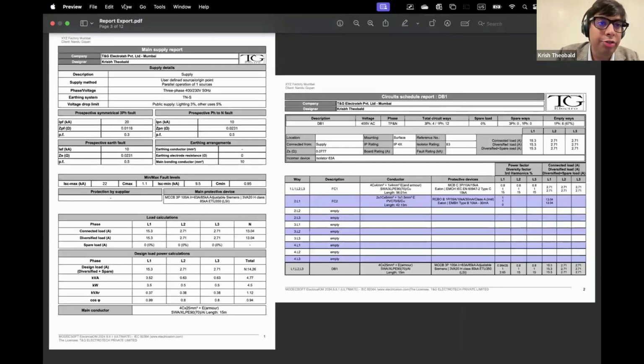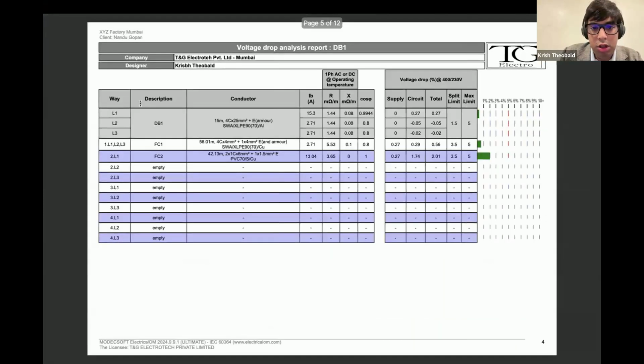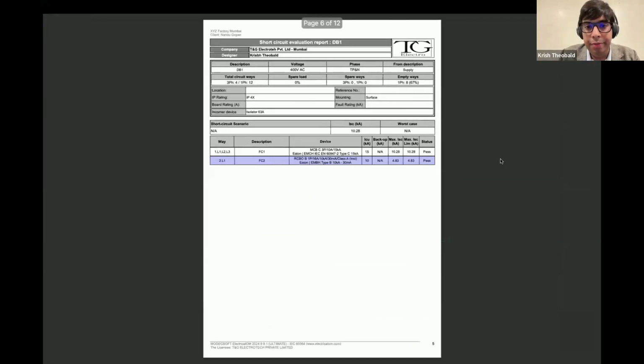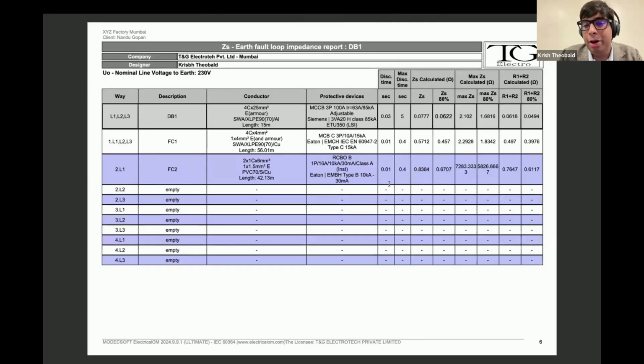So, it gives me all of this information. This is the cable used. This is the voltage drop we're getting. Now, does it pass the short circuit evaluation? So, this particular device is a 15K breaking capacity. This has a 10K. What is the actual short circuit current maximum? So, does it pass? This is the protected device. So, this is the time it will actually disconnect in. What is the maximum time we're allowed as per NEC? And it says IEC 60364 right now. This is the maximum loop impedance allowable. So this is where we're actually at. If you did it to 80%, this is where we're at.